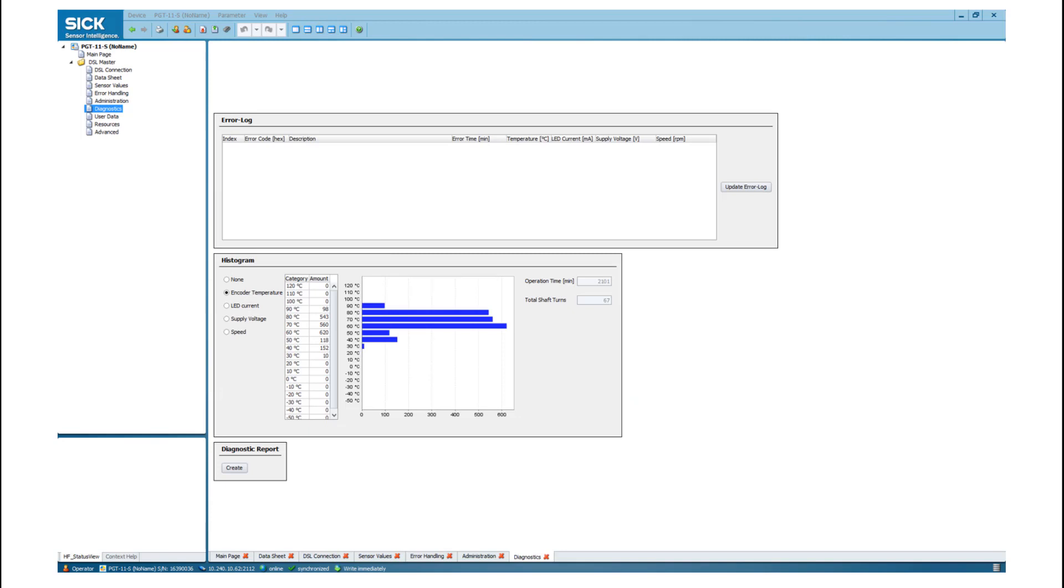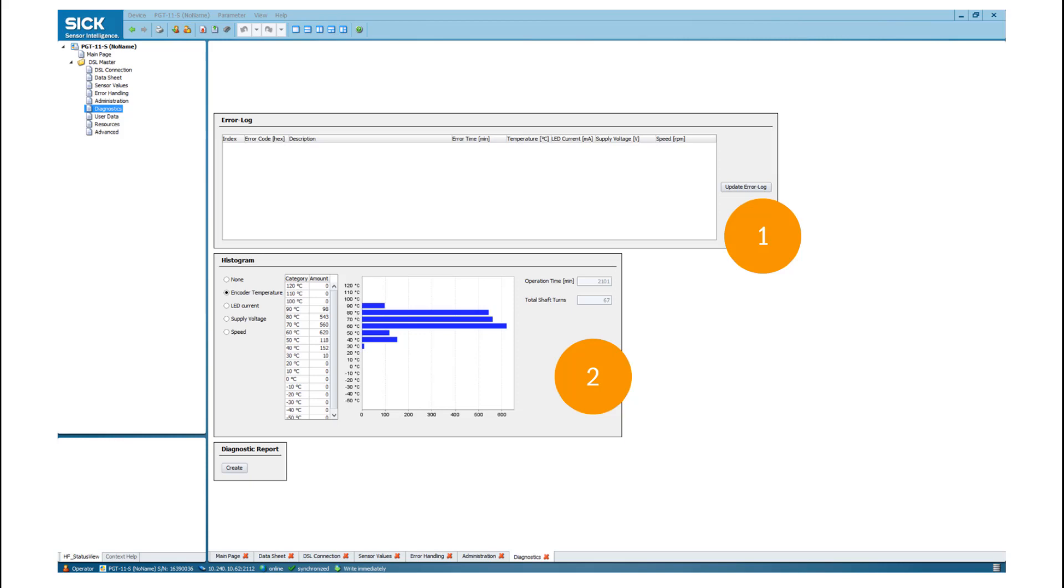In the diagnostics tab, the motor feedback system can be checked. If you push the Update Error Log button, all stored error messages will be displayed. The sensor can store up to 16 messages. Each Hyperface DSL sensor offers a histogram for condition monitoring. You can read out the encoder temperature, which was measured over the whole lifetime of the sensor.